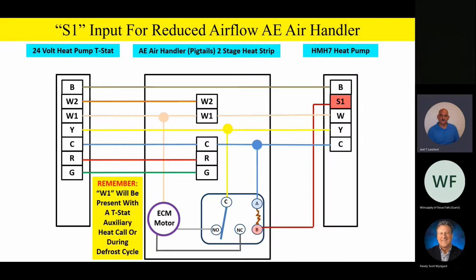Please note also a W1 call will be present with a thermostat auxiliary heat call or during the defrost cycle. So if this happened to be in a lower airflow condition and it went into defrost, bang, it's going to go on up to the high speed airflow that you have set on that speed tap number 5 when you get a W1 call. Any questions or comments on how this is working? The relay is going to allow us to have reduced airflow, but also if we have a W1 call, it's going to drive that fan to that high speed tap. Any questions or comments on any of that?